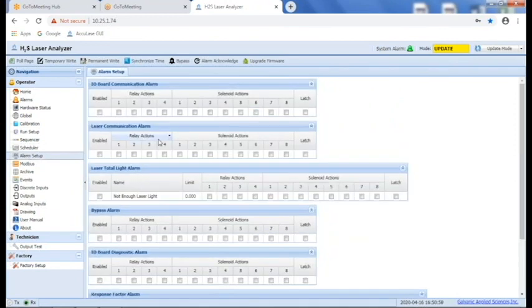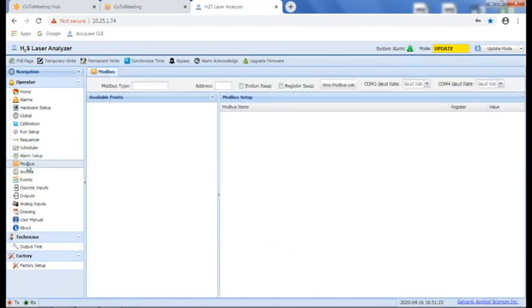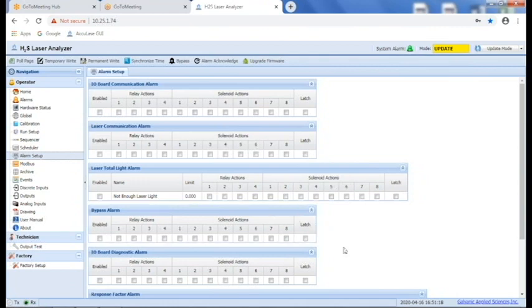There are some setups for the fault alarms, so you can see the different types of alarms we have available. If the I/O board stops communicating with the controller, the laser, for whatever reason, if it can't communicate, or if there's basically not enough laser light because the cell became fouled somehow, things like that. So these are the types of fault alarms that you can generate.